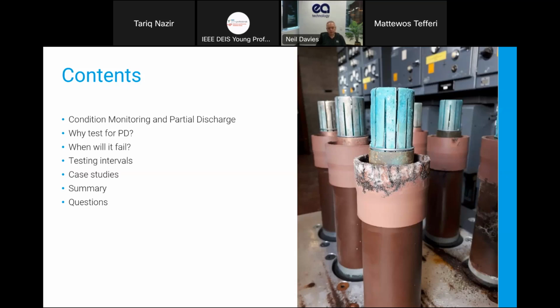And we'll look at different testing intervals and different regimes that people use. Because one of the common questions when companies start deploying testing techniques in partial discharge or any condition monitoring is how often should I do it? And it's always a balance between how often you test and whether you can catch failure. We'll explain that through real case studies, so we can show a couple of examples of where failure had happened or would have happened, and what different scenarios will catch them or not. Then we'll summarize, and of course take any questions at the end or in the chat.